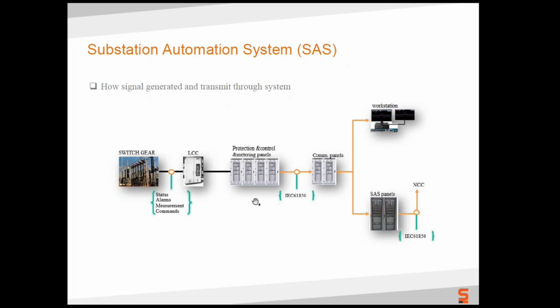Now all those parallel cables - imagine that earlier you needed 4 to 5 NO/NC contacts. Now you need only one contact of this switch, or for redundancy, let's say 2 contacts only. With this, a lot of cabling is saved, a lot of outage time, and also time tracing faults. Fault tracing is very important - once a fault comes, you have to trace it as fast as possible, especially in a 400 kV system, where power grid availability is always more than 97-98%. So you have to trace faults very fast and restore the system at the earliest. That thing becomes easy now.